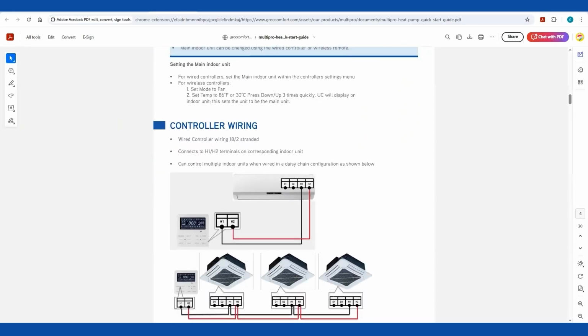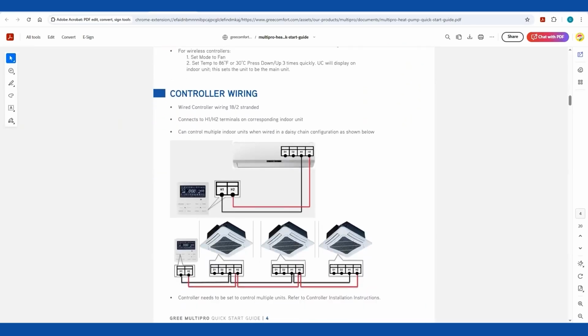Controller wiring. All of the GREE controllers come set up 1-to-1. In other words, this controller is set up to control one indoor unit. You can control up to 16 indoor units with one GREE controller. And it is done and wired in the daisy chain pattern, just like you would do the D1 and D2 wiring. You do your daisy chain like this. Now I can control all three of these units from that one controller.